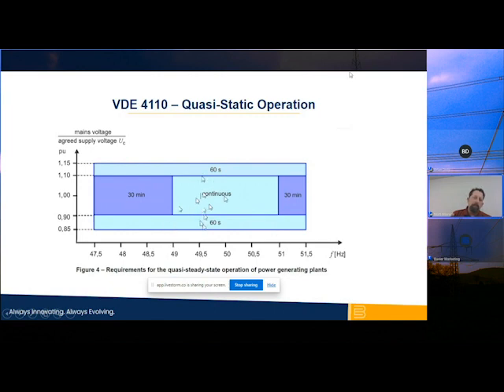So this is for grid support. If our voltage is more than 10% above or below nominal, this can define where we need to operate. This particular graph says if I'm between 1.1 per unit and 1.15 per unit, or 10% to 15% over, I have to operate in that condition for 60 seconds. Likewise, if I'm 5% below that lower limit, I have to stay connected for 60 seconds. So the voltage regulator needs to ride through these conditions for a minute if that happens. Now, if you look, the frequency is much longer. I also have set guidelines that I need to ride through, but they are set for 30 minutes.